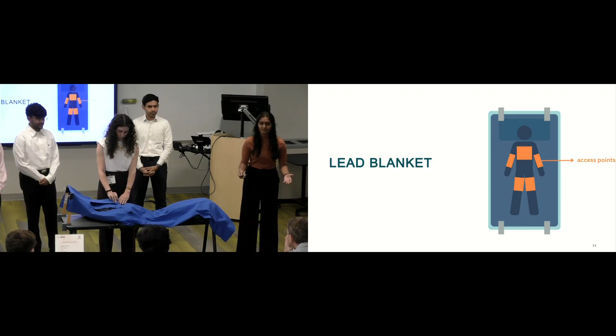Additionally, the blanket is suspended right above the patient at the source of the radiation scatter. Because when you look at fluoroscopy procedures, the X-ray comes from the bottom, and the radiation scatters right when it hits the patient's bone. So, by having the blanket suspended right above the patient, the radiation is contained at the source, which means there's going to be less radiation throughout the entire room. So, physicians would have to wear less shielding.